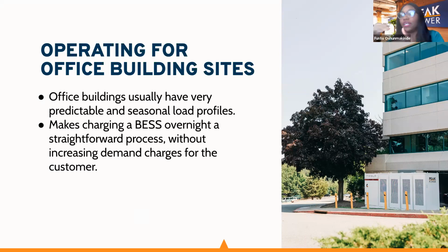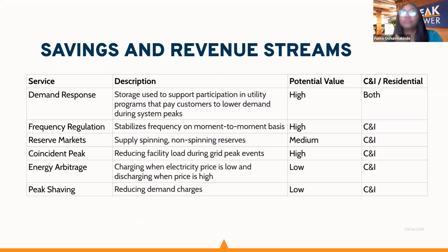So if you charge overnight, most times there's no risk of increasing the demand charges of the building. And also in terms of discharging, you typically want to discharge in the day where there's electricity demand, and thereby you can create savings for the customer and also reduce electricity bills. So I would hand it over to Archie now to discuss the savings and revenue stream.